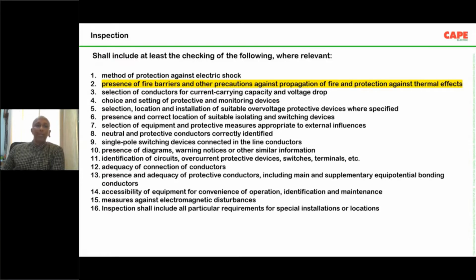Presence of fire barriers: based on the fire zone, once the cables cross the zone, we are supposed to have fire barriers. As a result of the fire barrier, fire in one zone will not pass to the other. Not only fire, fire and smoke are not supposed to pass to the other zone. And the last one here, protection against thermal effects. The thermal effect is about heat, how to handle heat in case of a fire. Then there are about 16 inspection points in all. I don't want to go much into it. Let me go to the next part, testing.